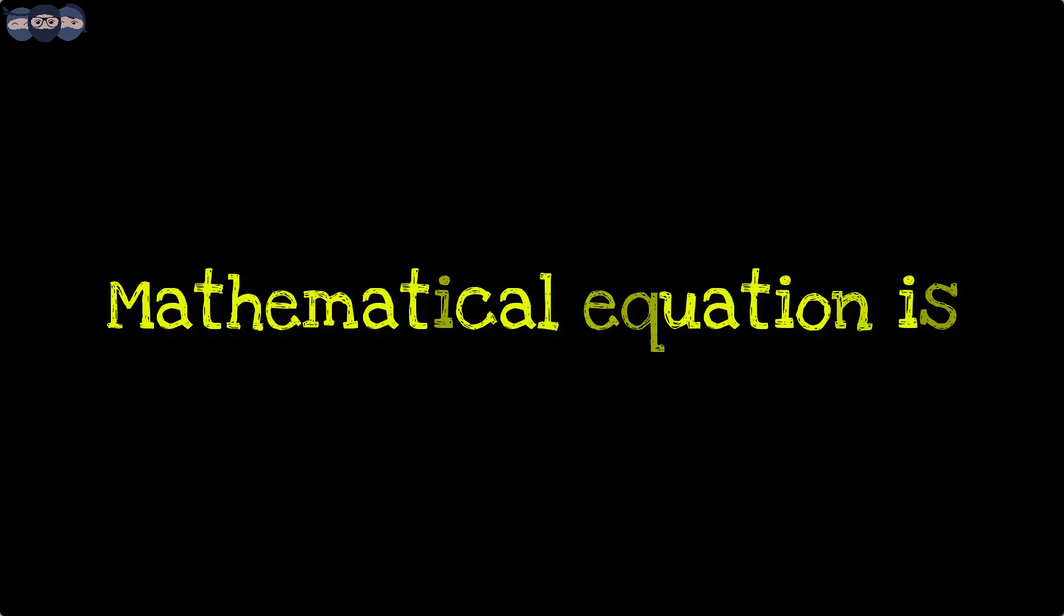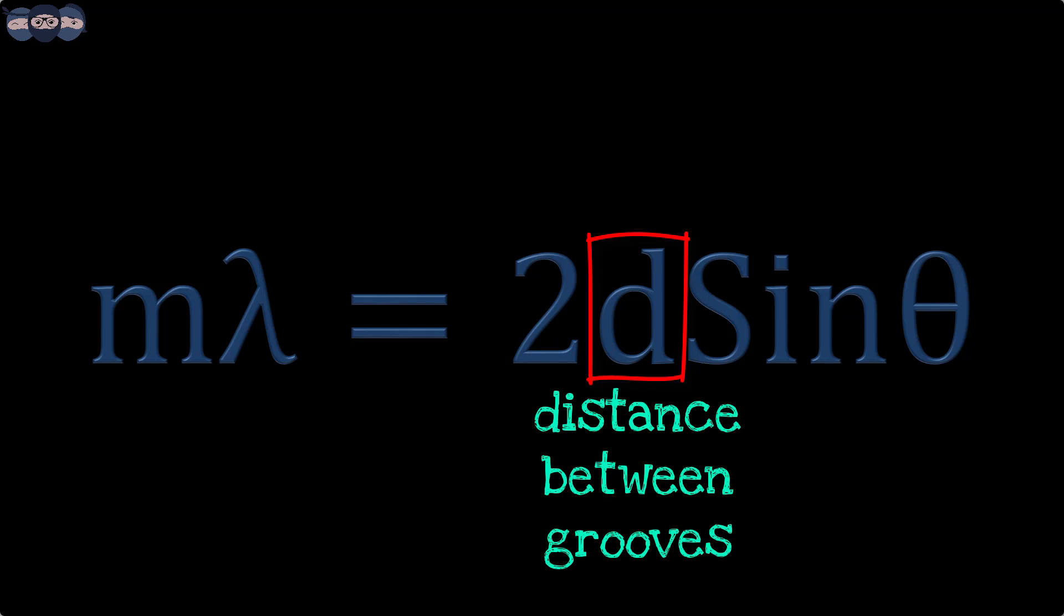The wavelength that can be obtained is given by the mathematical expression mλ equals 2d sinθ. For a fixed set of grooves with a separation distance of d, one can get the wavelength by rotating the grooved surface, i.e., by changing the angle θ perceived by the light.